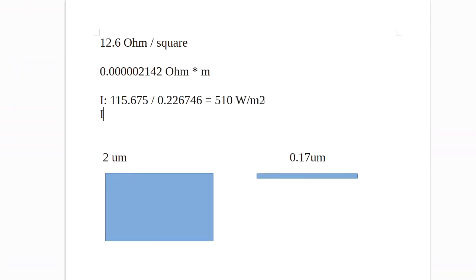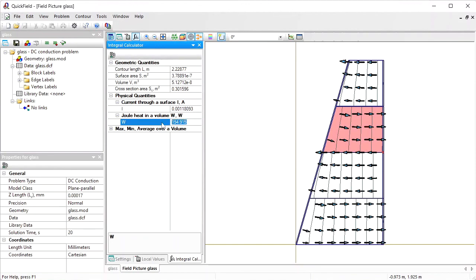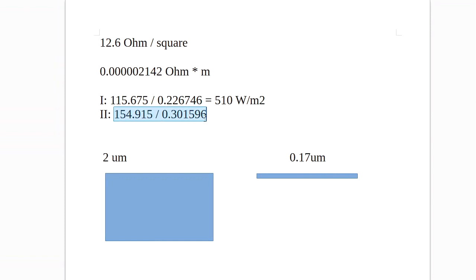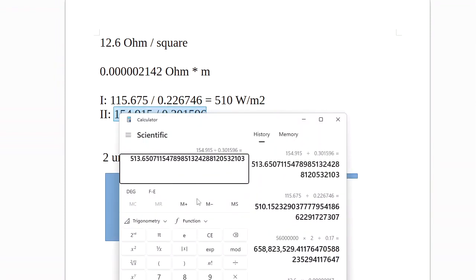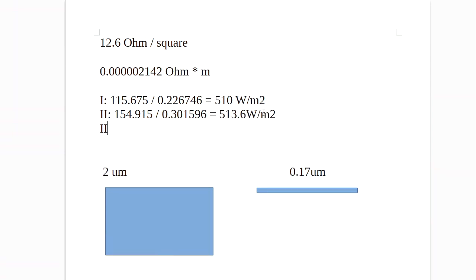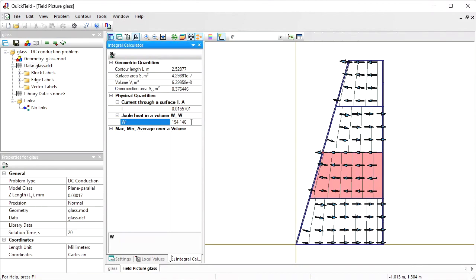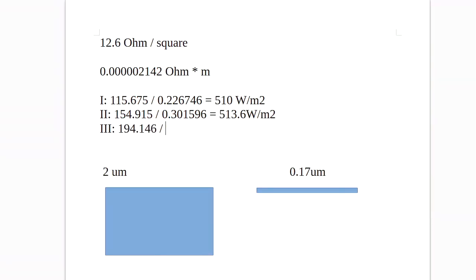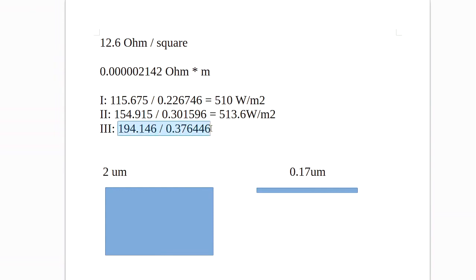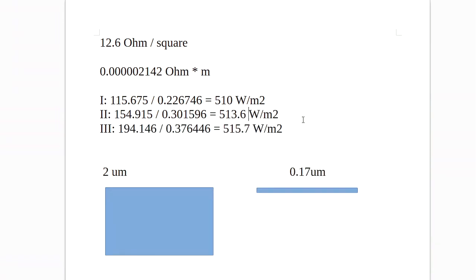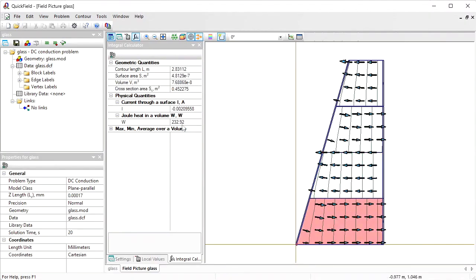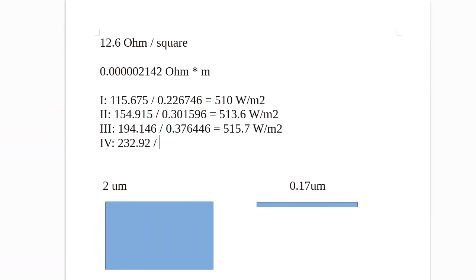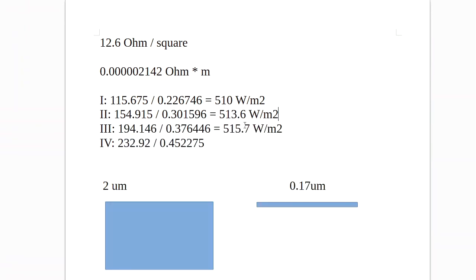Now what about the second section? Click to select the second section. This is the power, this is the area. So for the second section we have the power density of 514 watts per meter squared. What about the third section? 515 watts per meter squared. And the fourth section. 515 watts per meter squared. So we have more or less equal power dissipation in each section.